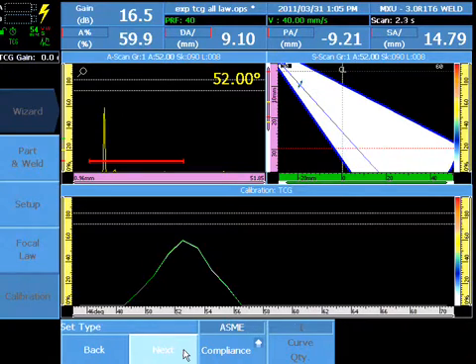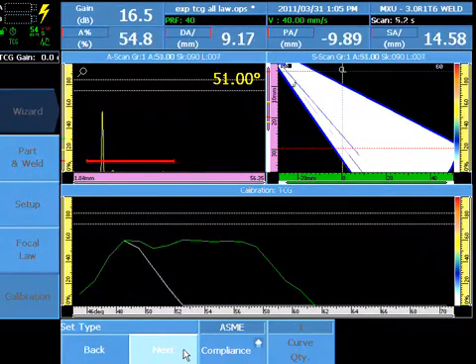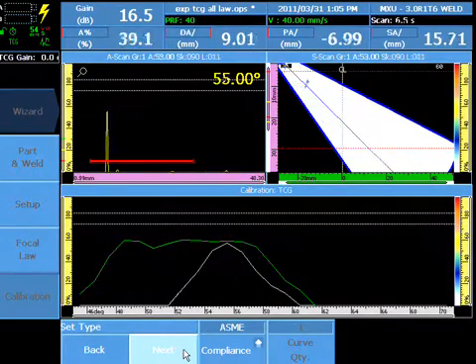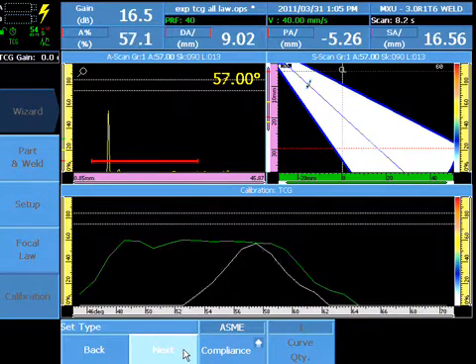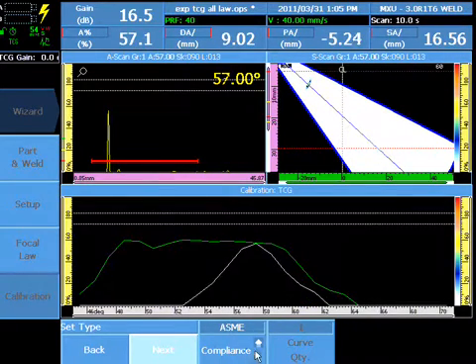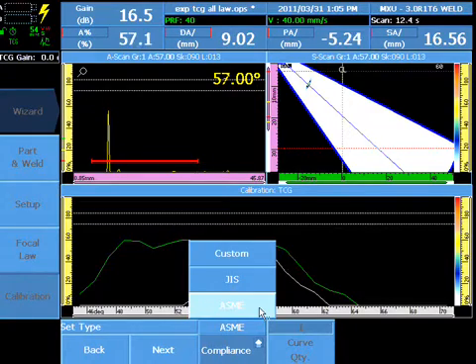Manipulate the probe so that the first TCG calibration target is present in the SectorScan. Select Compliance, ASME.